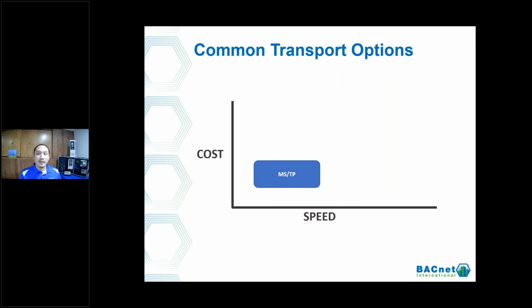What we're all familiar with is more Ethernet based, or BACnet IP, which is based off your Ethernet. It's becoming more familiar but still has a bit more cost to implement. The trade-off is you can get information faster. It really depends on what you're trying to implement and achieve when it comes to how you want to get that information across the network, physically.